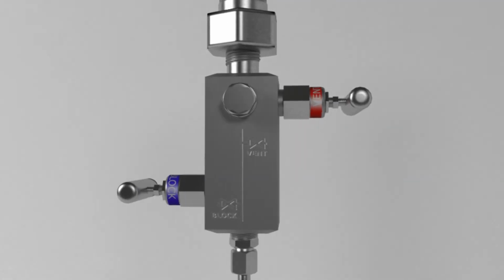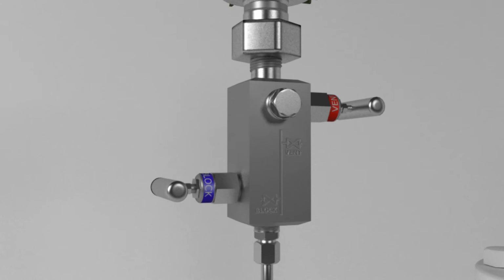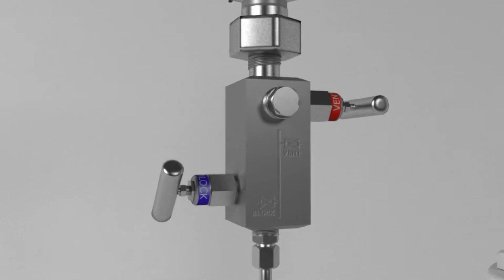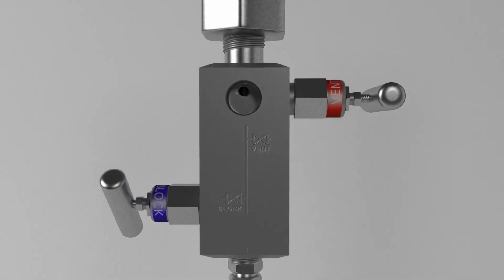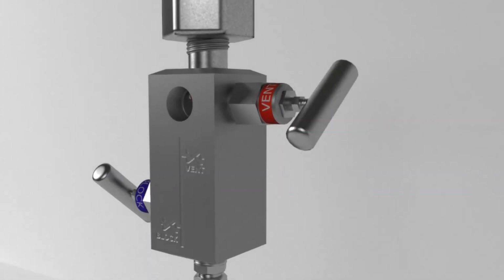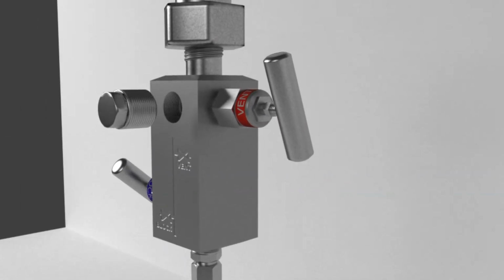To perform a calibration, close the isolation valve first. This isolates the transmitter. Next, remove the vent port plug. Then open the vent valve. Always remember to remove the vent plug before opening the vent valve.